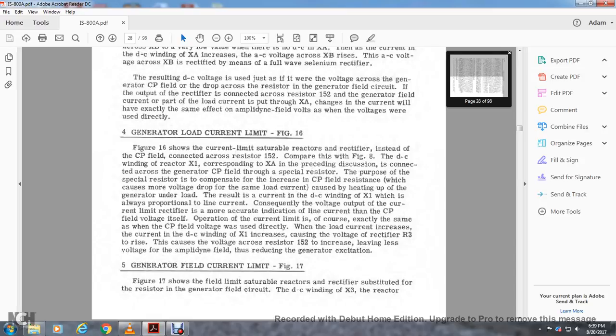Generator load current limit using saturable reactor with rectifier: figure 16 shows the current limit using a saturable reactor with a rectifier instead of the CP field directly. The DC winding with rectifier X1, reactor X1 corresponds to XA in the preceding discussion. The DC winding is connected across the generator CP field through a special resistor whose purpose is to compensate for the increase in CP field resistance, which causes a larger voltage drop for the same load current because of heating of the generator under load. The result is that the current in the DC winding of reactor X1 is always proportional to the line current. Consequently, the voltage output of the current limiting rectifier is a more accurate indication of the current than the CP field volts themselves.